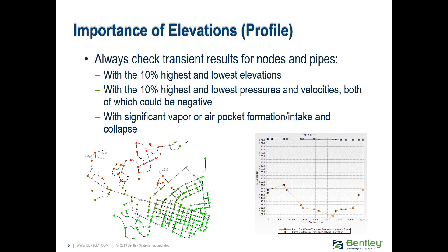Here's an example of the importance of elevation. To check your results, you can use flex tables, sort them by elevation, and check your highest and lowest points. You can open up a junction table, sort on elevation, and focus on those particular elements. A profile in the transient results viewer may only cover one path, so there might be significant high or low points elsewhere in the system that you're not covering in that profile path.